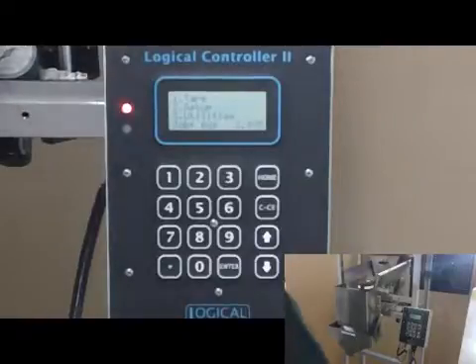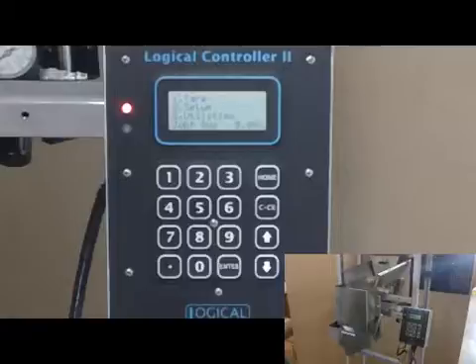We want to verify the calibration by removing the weight from the weigh hopper or the table scale to make sure that the scale returns to zero. You can see that we have about three thousandths, two to three thousandths registering on the weigh hopper.